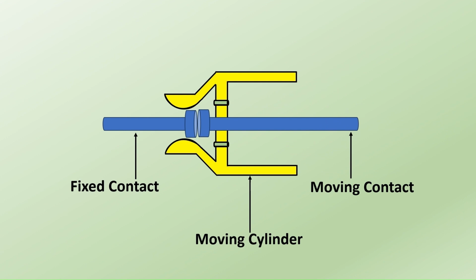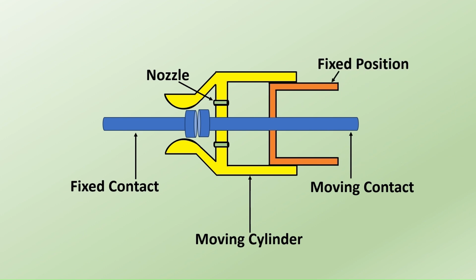A nozzle is made available on the piston of the moving cylinder to allow the SF6 gas to flow. A fixed member is connected at the back side of the moving cylinder. Non-compressed SF6 gas is placed between the moving cylinder and the fixed member.